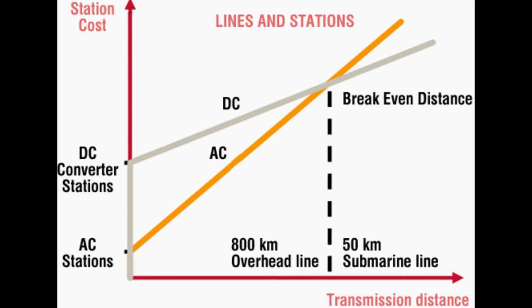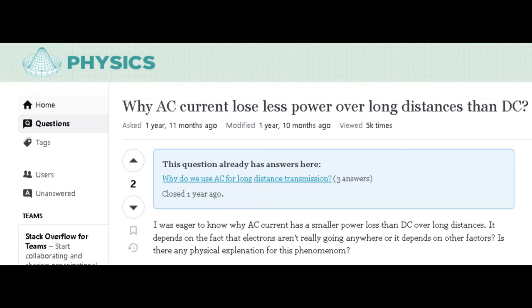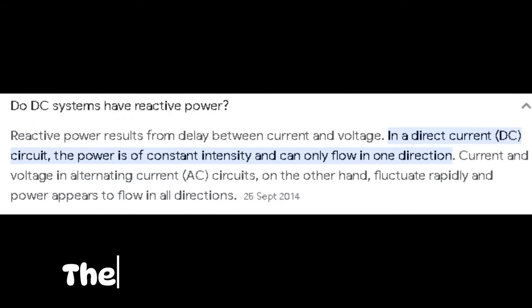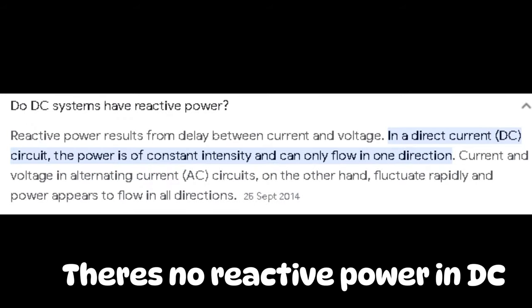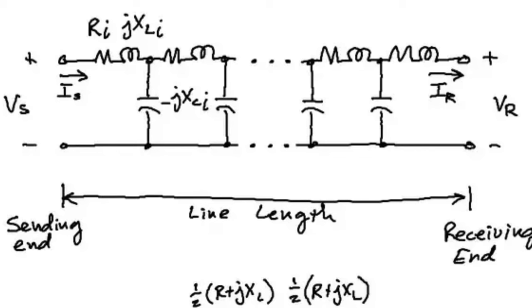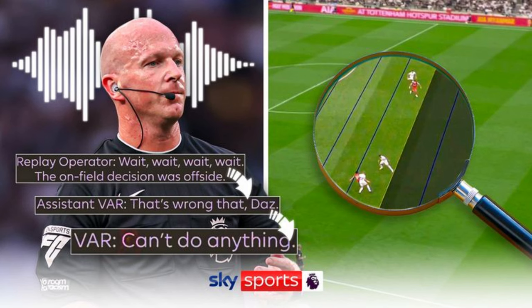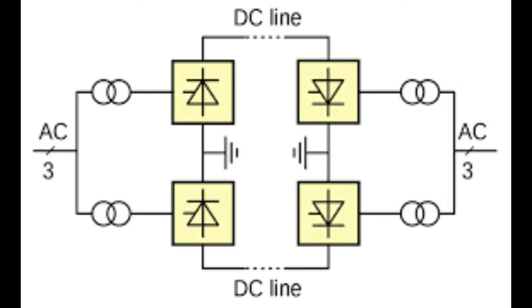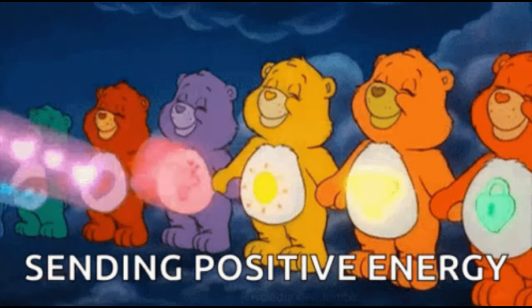Transmitting power over long distances is tough for AC compared to DC because DC doesn't need to transfer any reactive power — there is no reactive power in a DC connection. In super long AC lines, reactive power becomes highly influential. The VAR can be hard to control and also eats up transmission line capacity that is meant for transferring real power instead. DC connection gives you ultimate control — you can set exactly how much power to send, with none of the power oscillation problems.